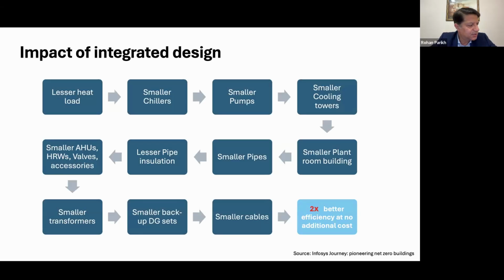Yes, of course. So what we do is dramatically reduce the velocity in all the air handling units. The AHU coil size, the face of the coil, is designed fairly large - typically design standards earlier were 500 FPM, and what we design for is 250 FPM. So the air moving across the coil is so slow that it's pretty much laminar.